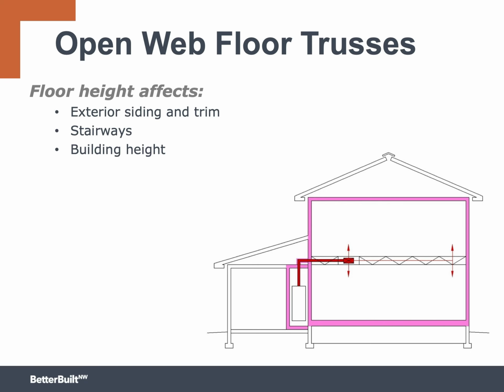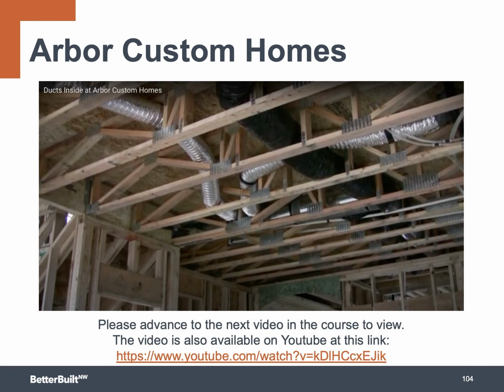Many builders place the furnace on the second floor and use a downdraft furnace connected to supply ducts running through the floor trusses. The return runs a very short distance through the attic. This approach also works well with first-floor mechanical rooms and garages because an upflow furnace can feed a supply trunk that runs between the floor joists. Now let's look at another video where we go through a house that was built by Arbor Custom Homes and see how they've installed the open web floor trusses.